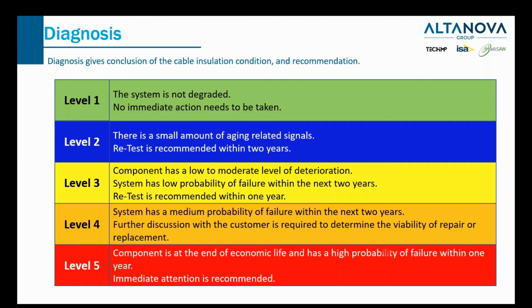Here is an example of a 5-level system that we use for medium voltage cable testing and evaluation. Level 1 is the best condition, no degradation, no action needed. And level 5 means the component is going to fail in a very short time. We need to take action immediately. Levels 2, 3, and 4 are in the middle. So with the level system, the customer can prioritize the maintenance plan and take actions based on the priorities. This is quite unique and helpful information for the clients.